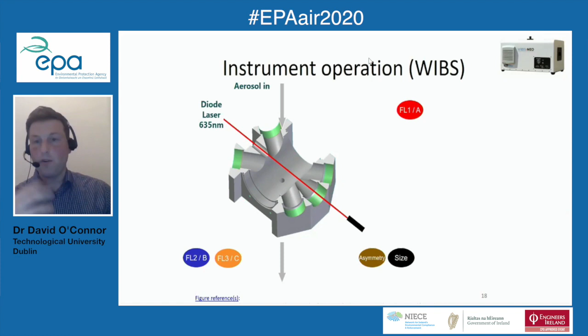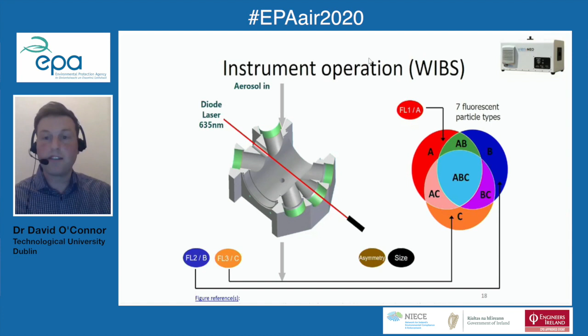Of course, the particle then exits the instrument, and the whole thing repeats itself, and it can do that up to 200 times per second at millisecond resolution, so far faster than the traditional techniques. You can then combine all this information on the particle, and if it's only fluorescent in the FL1 channel, it's deemed an A particle. If it's only fluorescent in the FL2 channel, it's deemed a B particle. But of course, it could be fluorescent in both. This Venn diagram just shows you the 7 different characterizations you can have for fluorescent type particles, and that's the category analysis that we applied to our data.